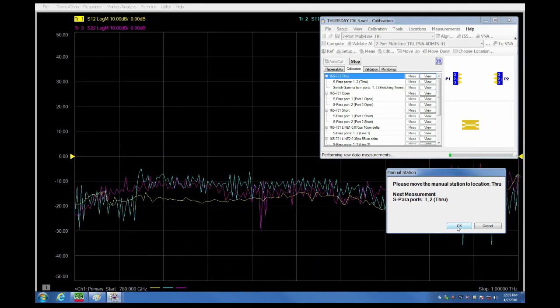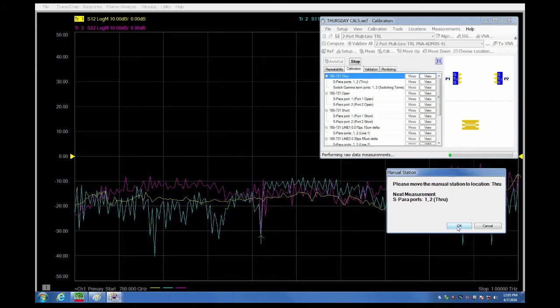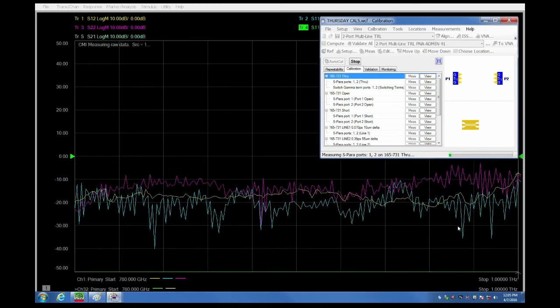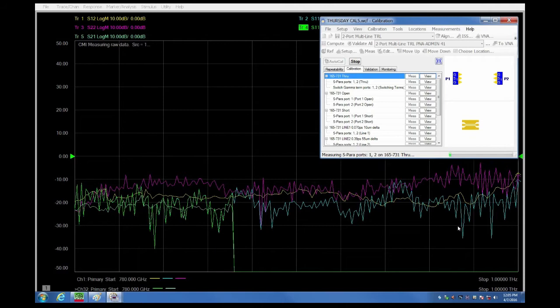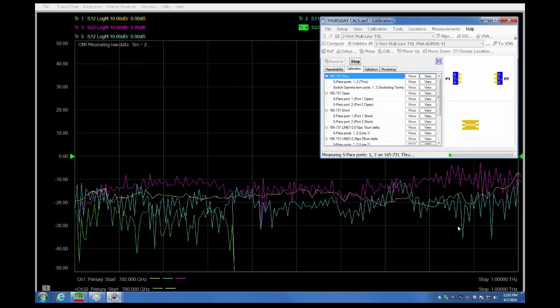You will note that the trace changes once the probes have actually made contact. WinCal will automatically measure the S parameter terms between ports 1 and 2 after which it will then measure the switching terms.